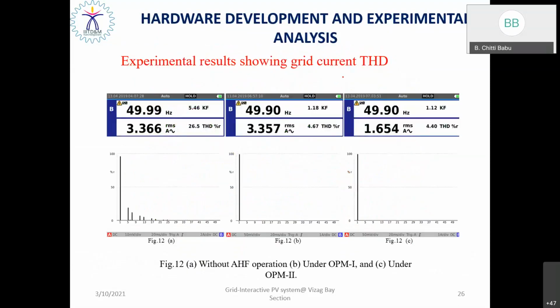You can see the harmonic spectrum of the grid current as it injects only the fundamental current component, and without controller you can see it has a lower order harmonic component with a THD of 26.5%. With the help of the active harmonic filtering capability, the THD has been reduced drastically to 4.67%. And further, with the multi-purpose inverter, the THD has been further reduced to 4.40%.